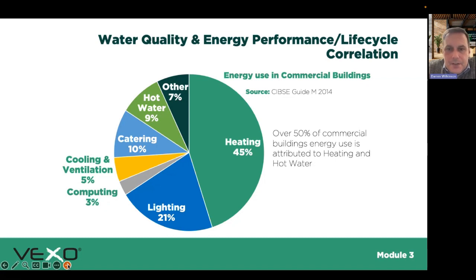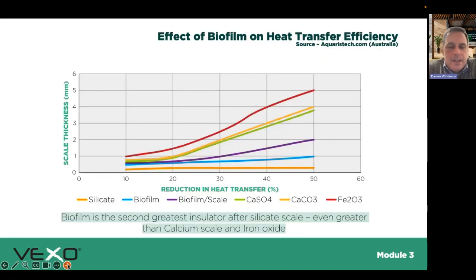You could be losing efficiency because your pumps are working harder, your strainers are getting blocked, so your pumps are ramping up. Your heat exchangers or your boilers are struggling. So people generally, I've seen over the years, turn up the temperature stat on the boiler and so on, to try and push heat around. So there's a huge amount of savings that can be made on energy just by having clean systems.